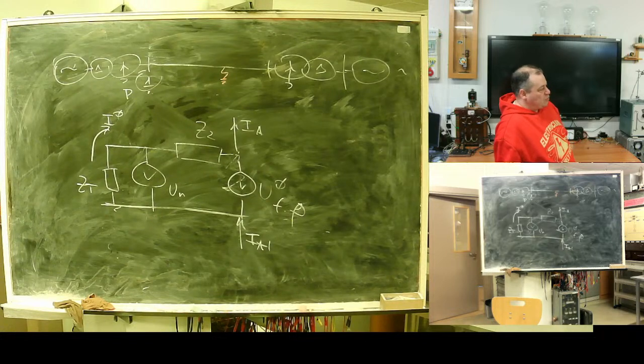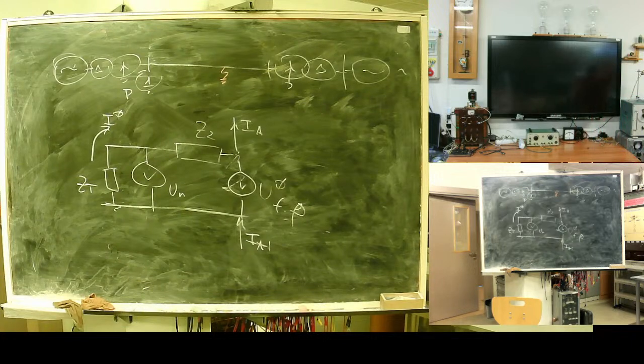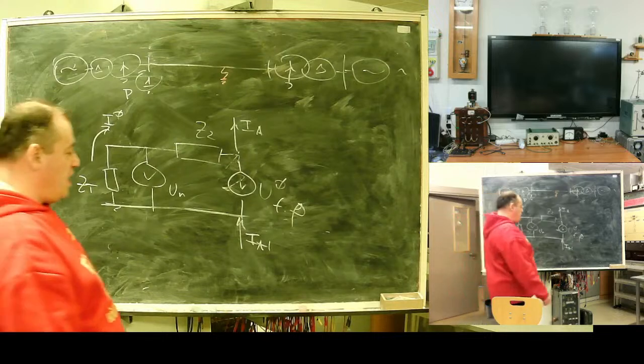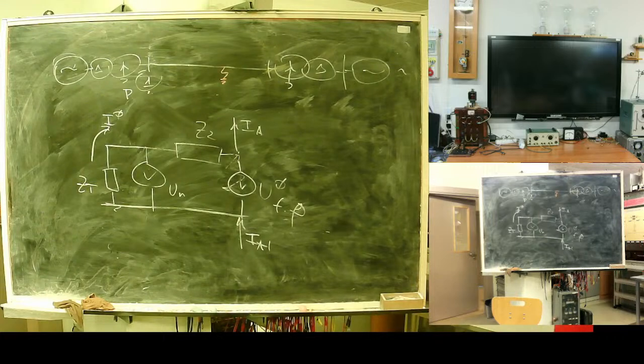Anyway, in case of close fault, you will have voltage. So sensitivity problem goes far. This kind of protection usually does not suffer from sensitivity problem in case of near fault. The closer the fault, the higher the signal. Anyway, it's a good practice to predict switch on fault condition.